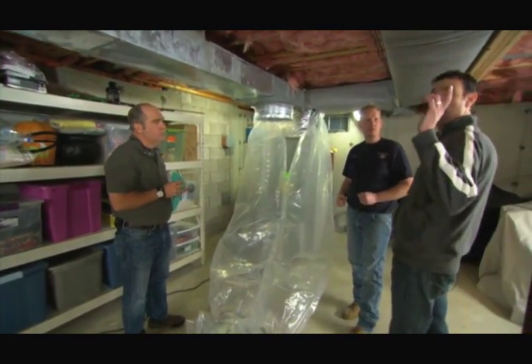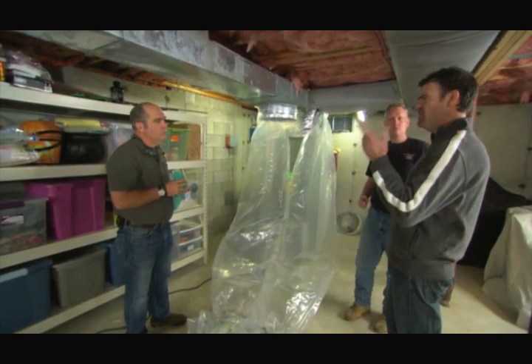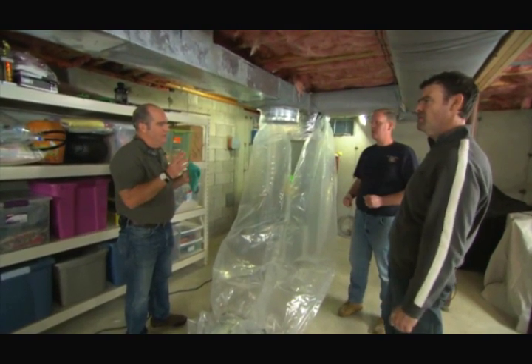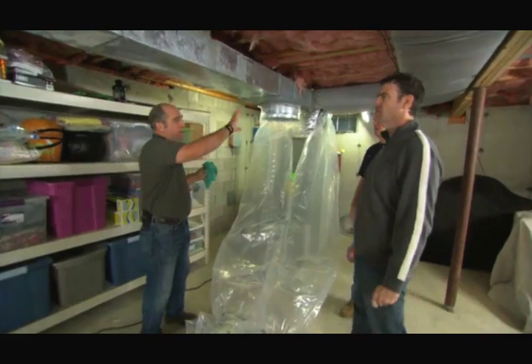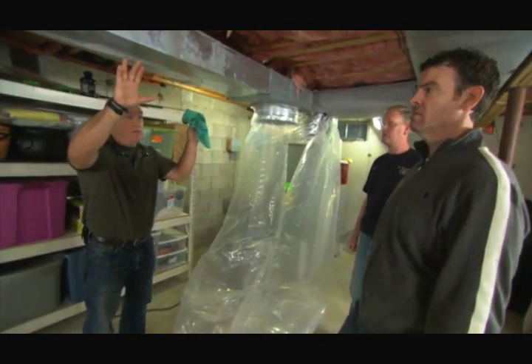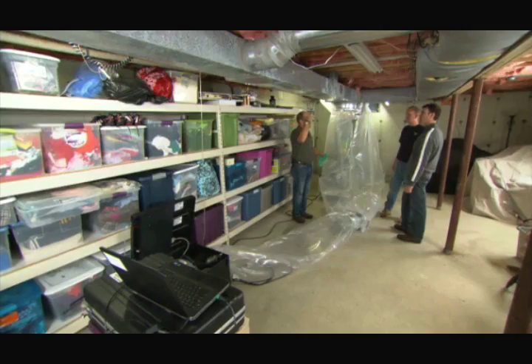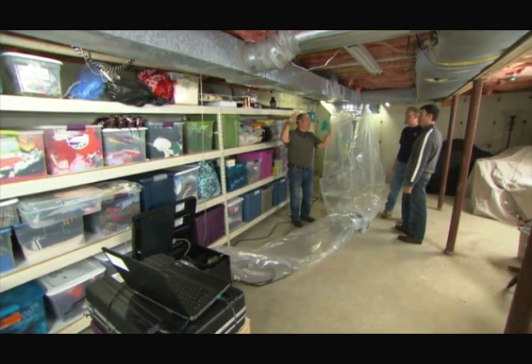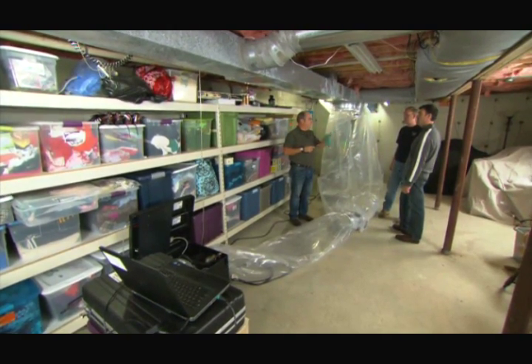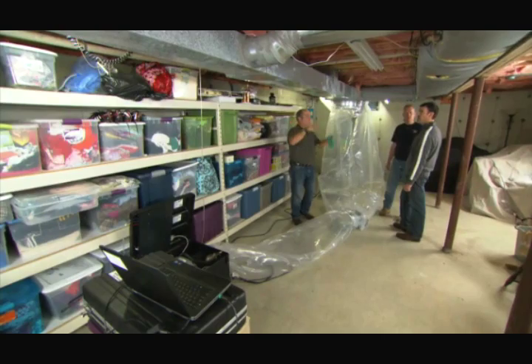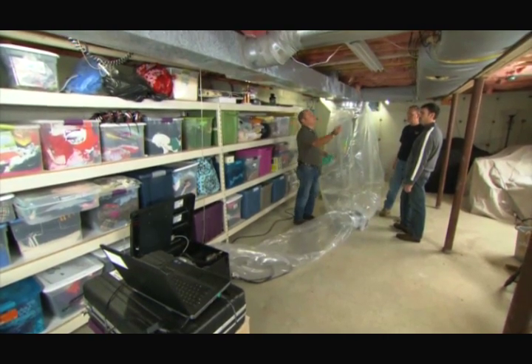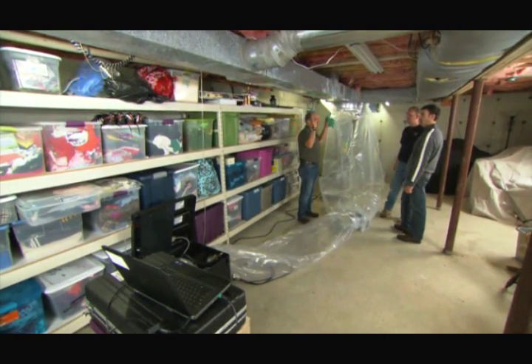So I understand why we would seal the supply, but why do we seal the return? Well, think about it. You got heated air coming out here. We want to keep that in the ductwork. On the return side, it's under a negative pressure, so it's pulling air in. Remember you complained about dust? Yeah. Well, if these leak and there was any dust down here, it would be sucked into the ductwork and then distributed all into your house.